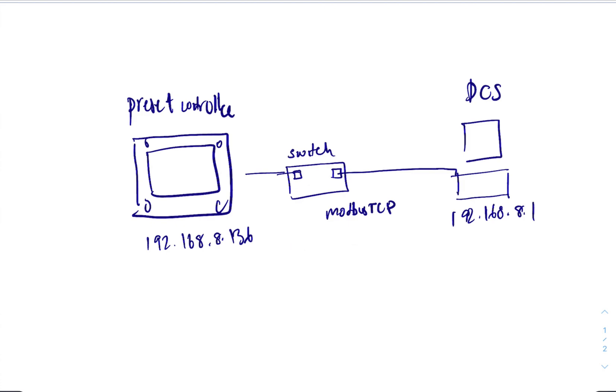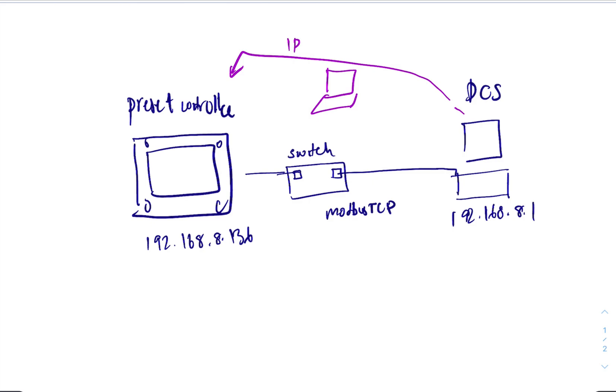Because DCS is communicating with one particular IP, right? And then if you put your laptop in between, two devices on that same network cannot have the same IP. If it has the same IP, it's going to say IP conflict and the computer is going to take a default IP that will not work.